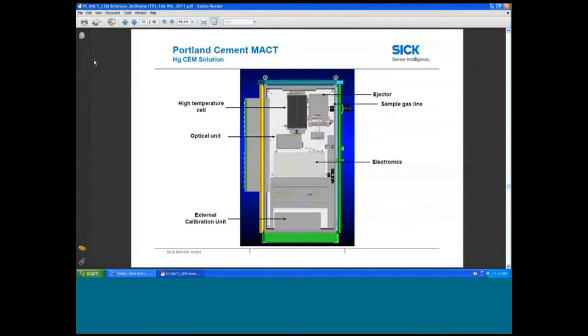I mentioned we were going to go to a high temperature conversion concept. And so we've got a cell that we heat to about 1,000 degrees C, and we're doing the conversion to elemental mercury and measurement in the same location. So we can eliminate any worry about possible recombination in the sample system. And then below that, of course, we've got the optical unit with our light source and detector, and then the external calibration unit and all the necessary electronics that are required for a standard CEMS.